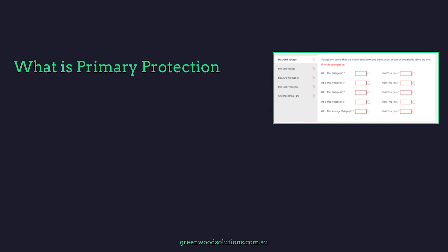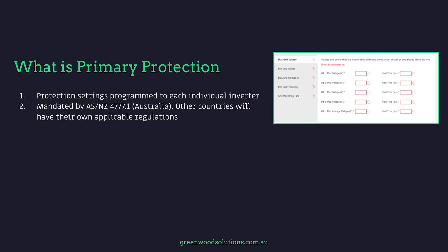So let's have a look at primary protection. These are the protection settings programmed to each individual inverter — max voltage, hold time, etc. It's mandated by AS 4777.1. Australia, New Zealand and other countries will have their own applicable regulations. And settings may vary from each DNSP — distribution network service provider — so make sure that when you're dealing with your specific DNSP that you have all the correct settings.